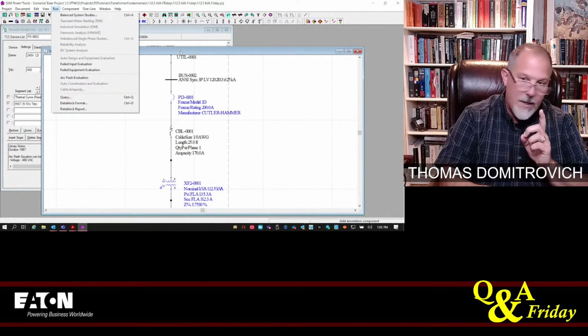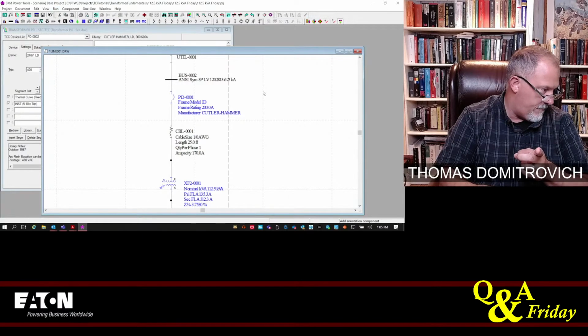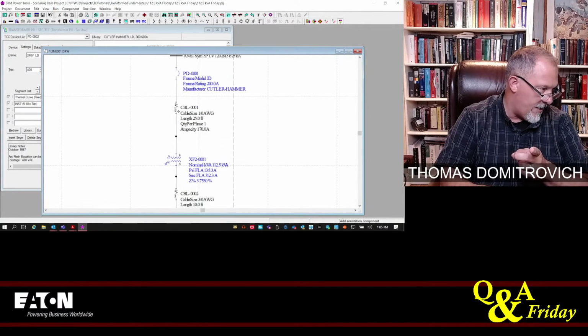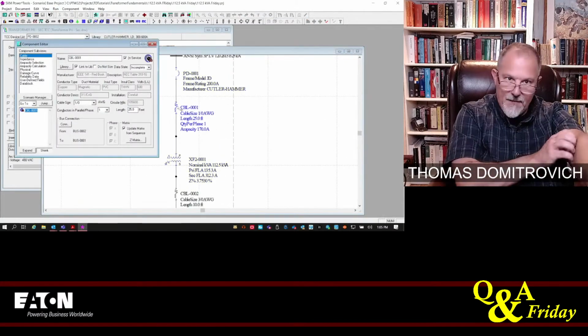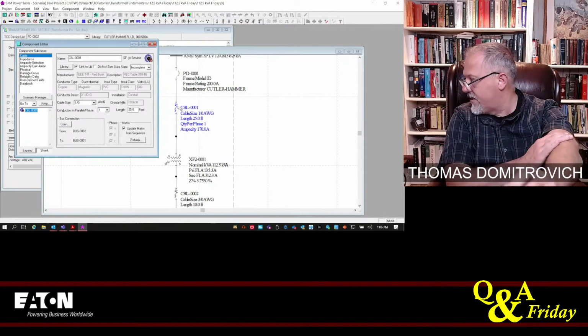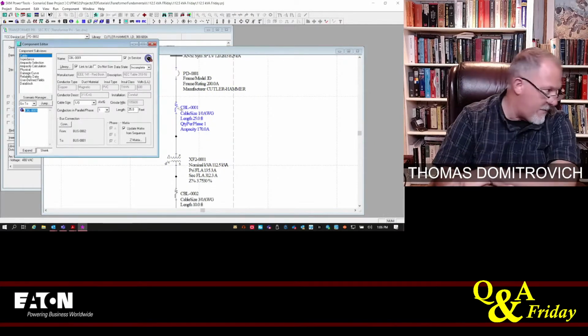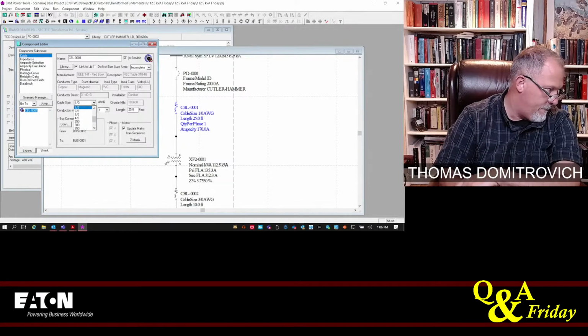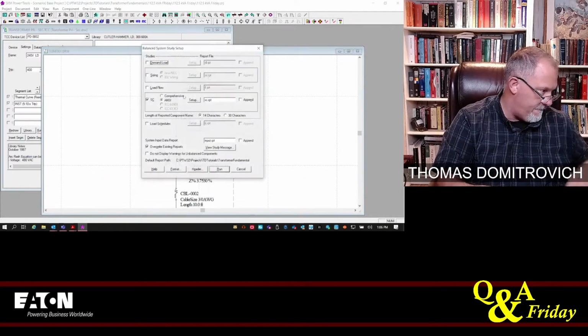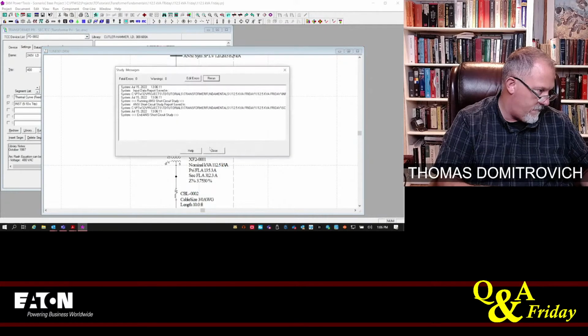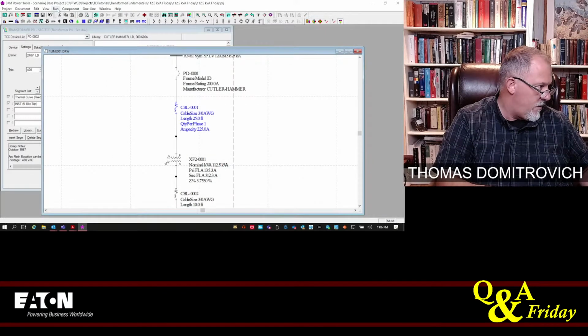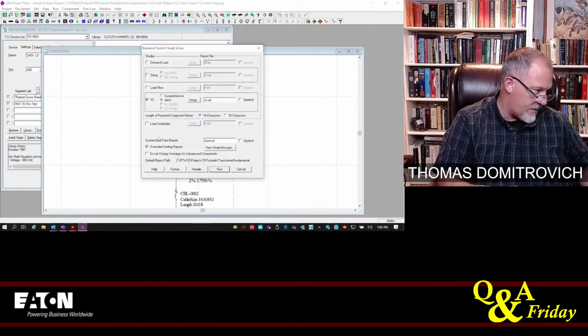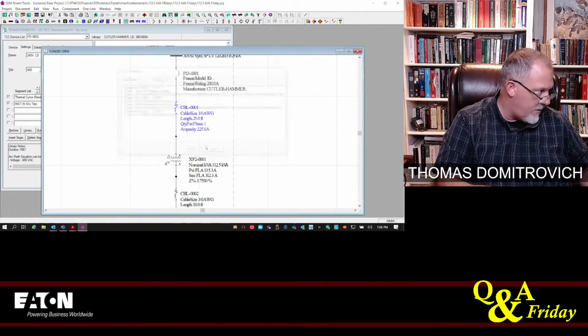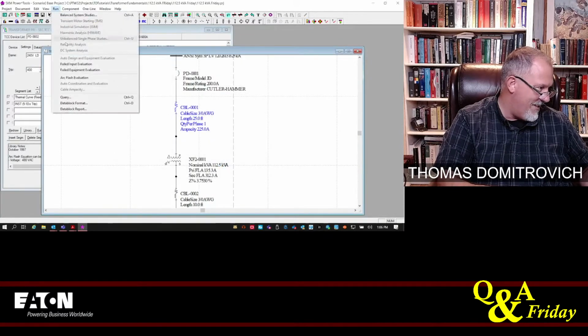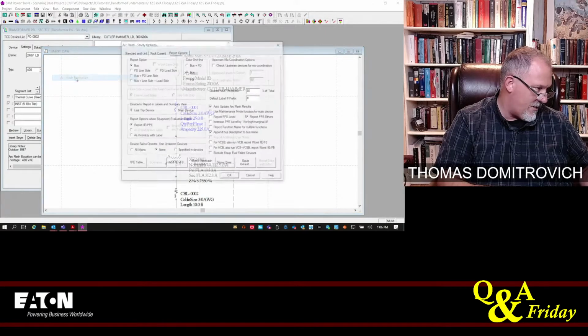Oh no, what did I do? I changed the primary to 200 amps, but I left 150 amps worth of conductor, so I got to make this a 3-aught. And then I need to rerun the short circuit study. Run, close, run, balanced system study, run, close, run, arc flash evaluation.